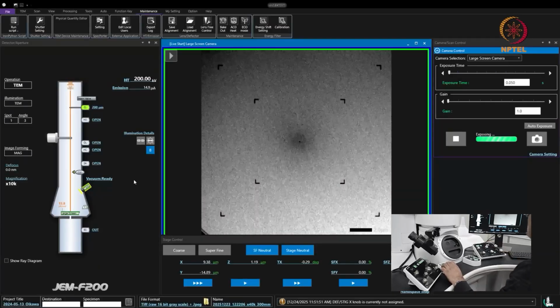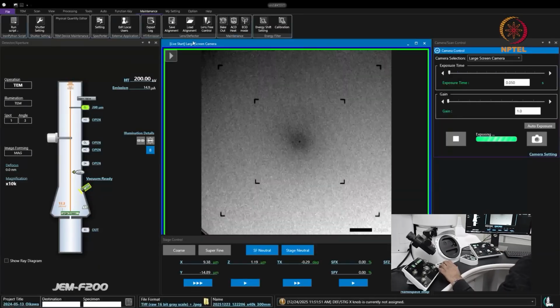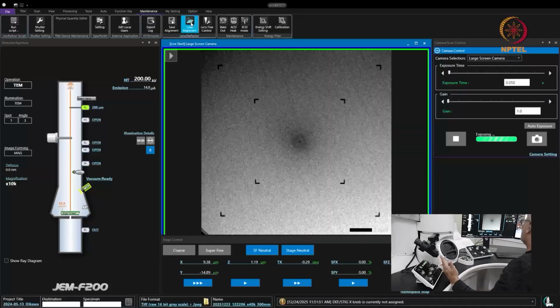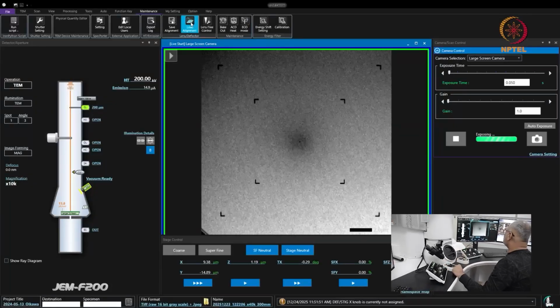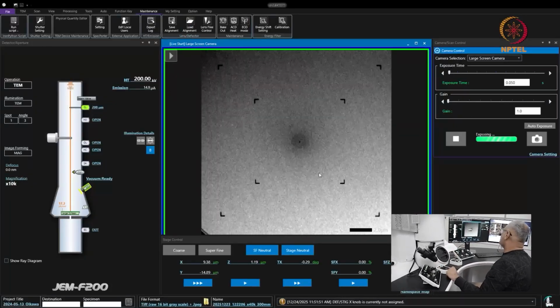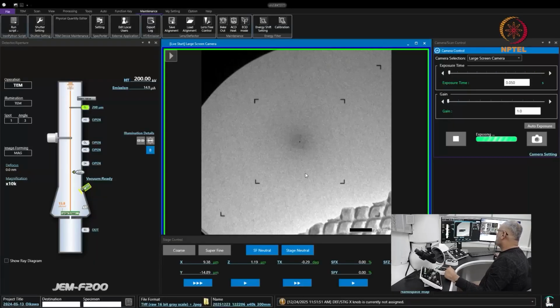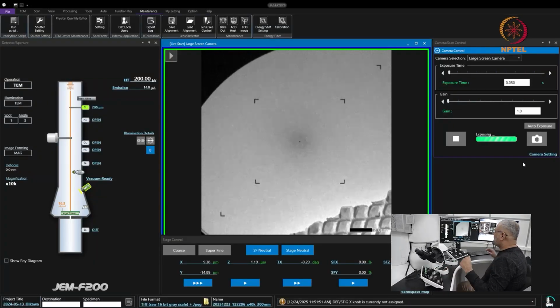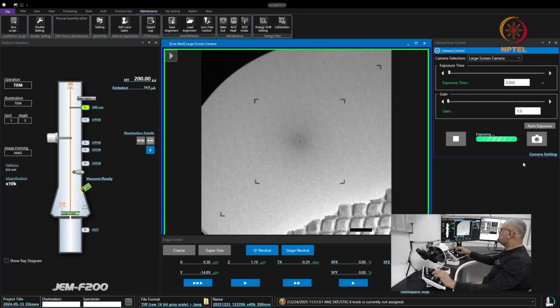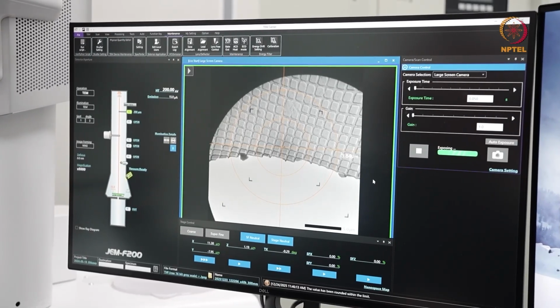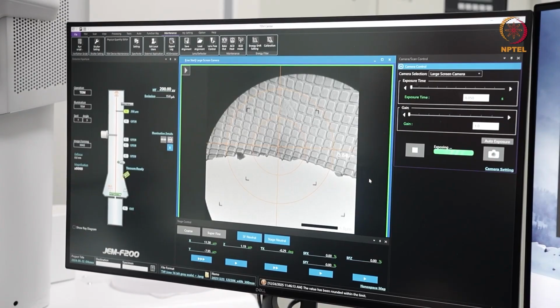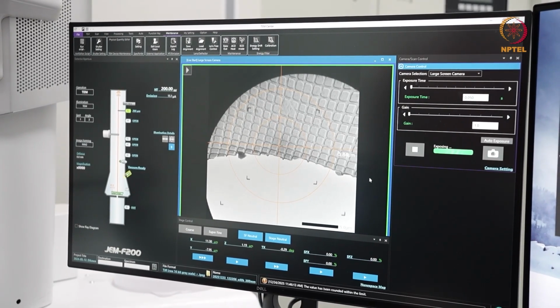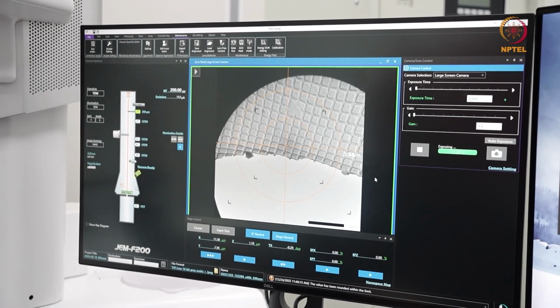And what you can do is, if your instrument is maintained regularly and has preloaded alignment files, I can always load the previously existing alignment file. And then even after you load this, you should do some basic corrections. So the first thing that I would do is bring your area of interest into the eucentric height, or you could also start by correcting the alignment of the condenser aperture.